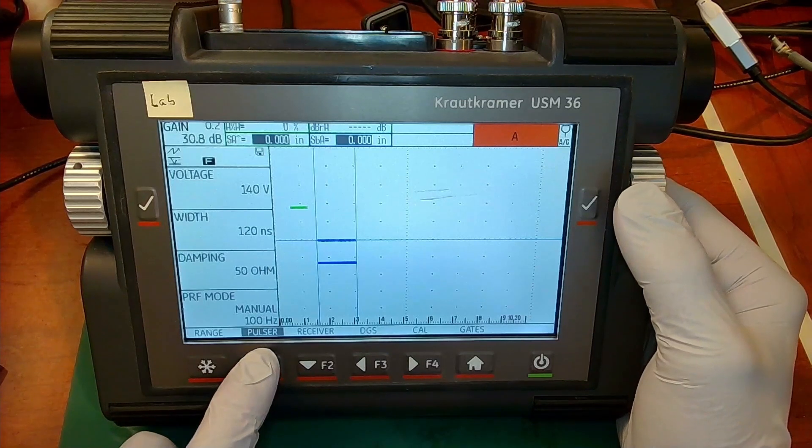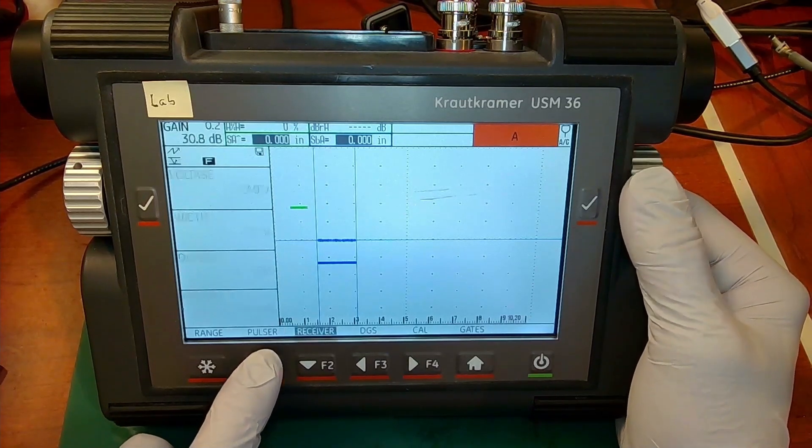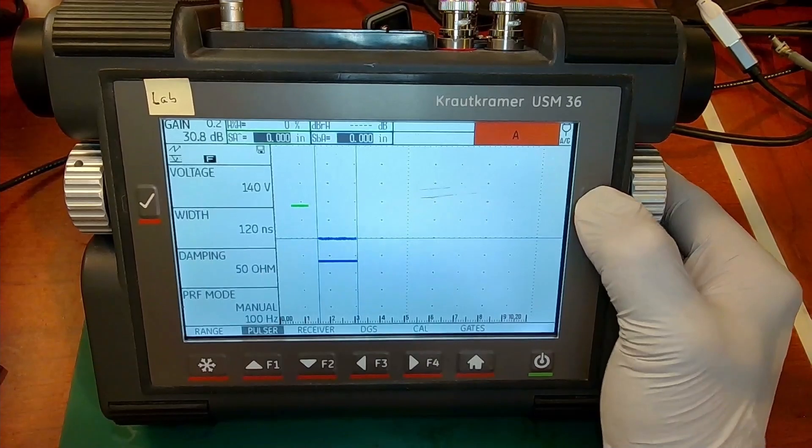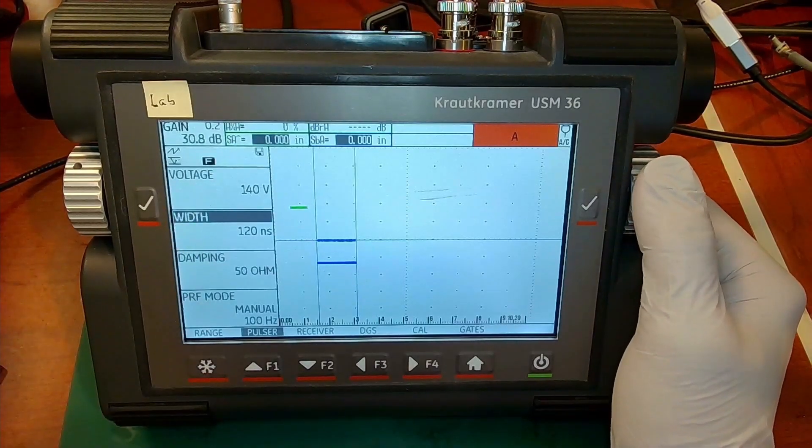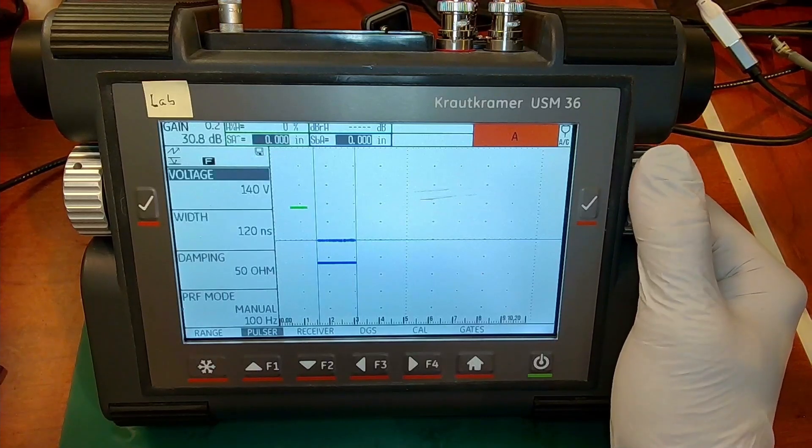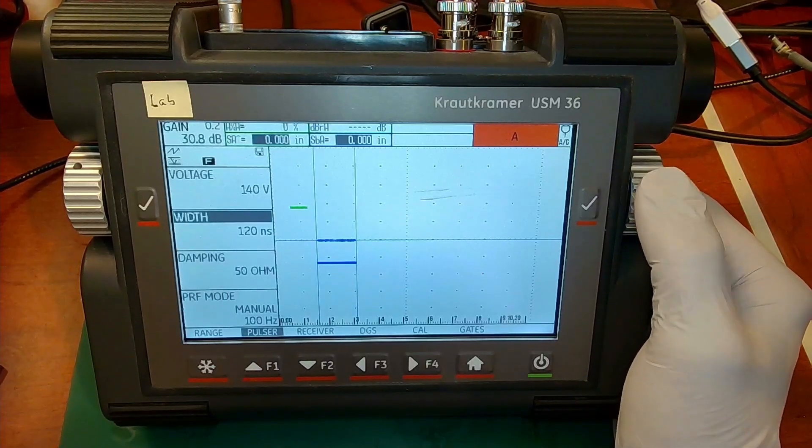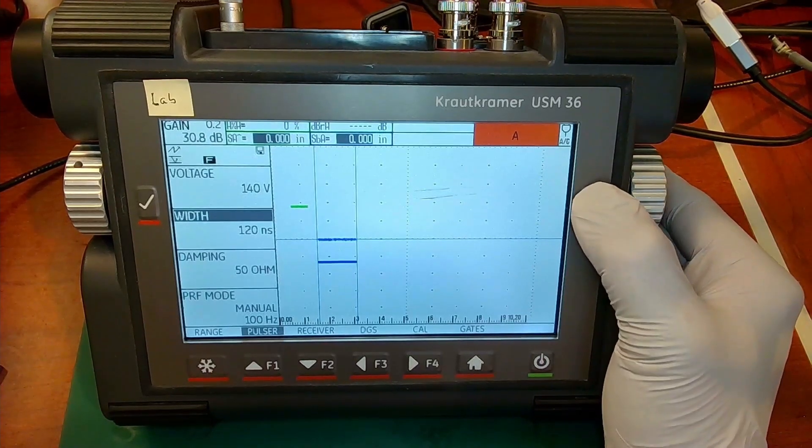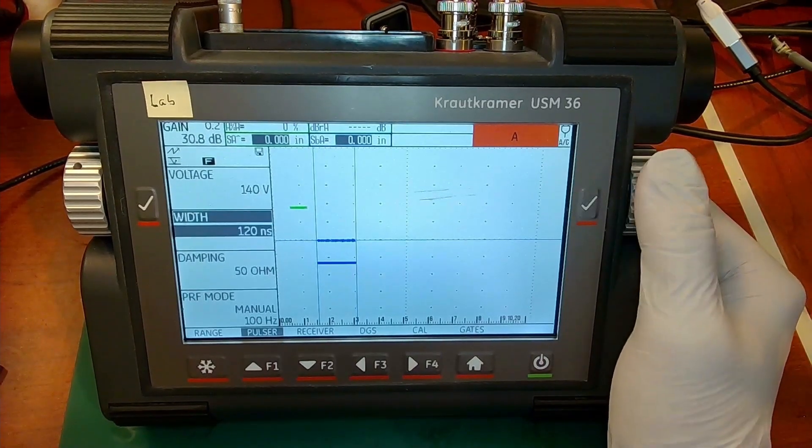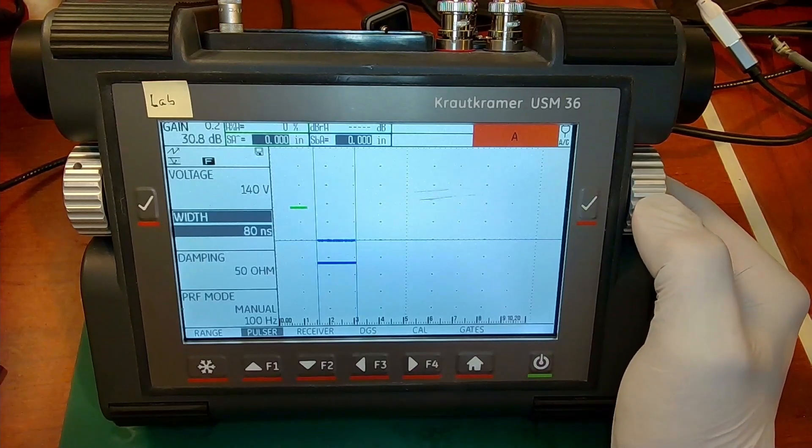But normally you would navigate from menu to menu with the right knob. Let's say we wanted to change the setting on the pulser menu. We would use the right knob to get to the pulser menu, hit the check box. That moves the cursor up onto the menu. And now the right knob is selecting a parameter within the menu. Let's say we want to change our pulser width. And we hit the check mark one more time to activate that control.